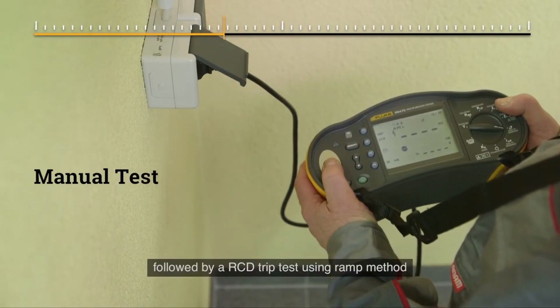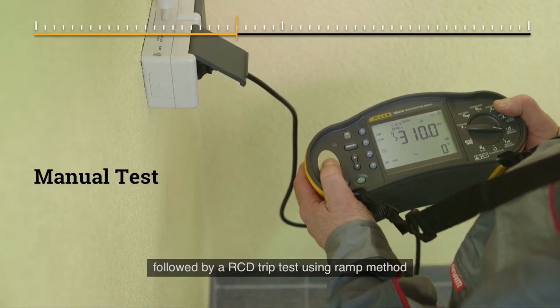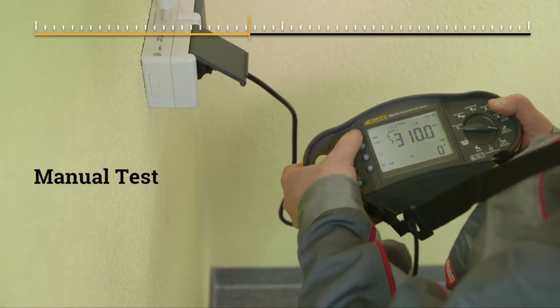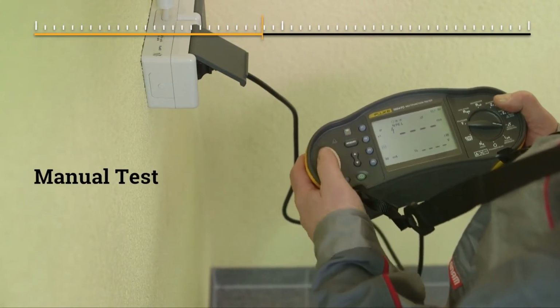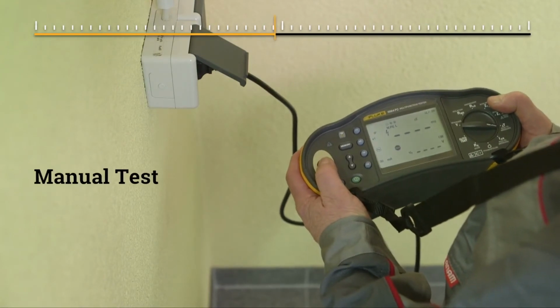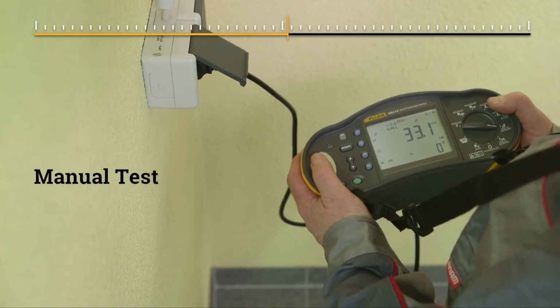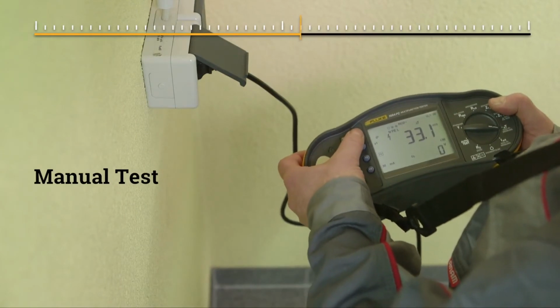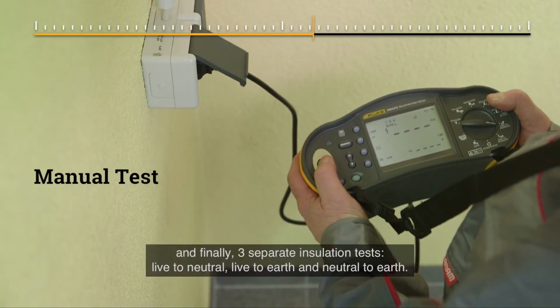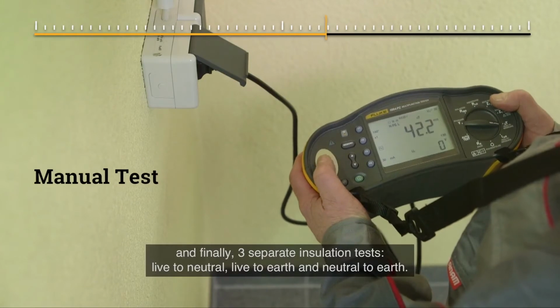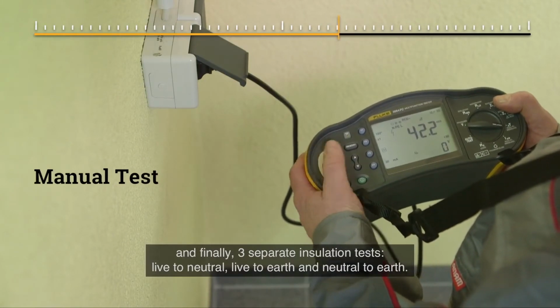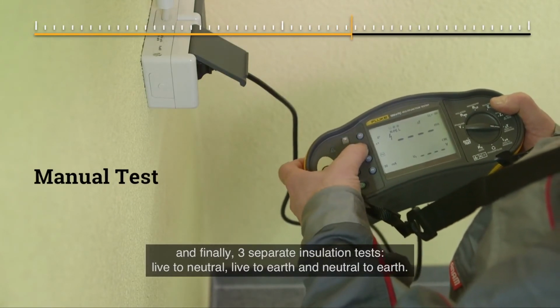Followed by an RCD trip test using ramp method. And finally, 3 separate insulation tests: live to neutral, live to earth, and neutral to earth.